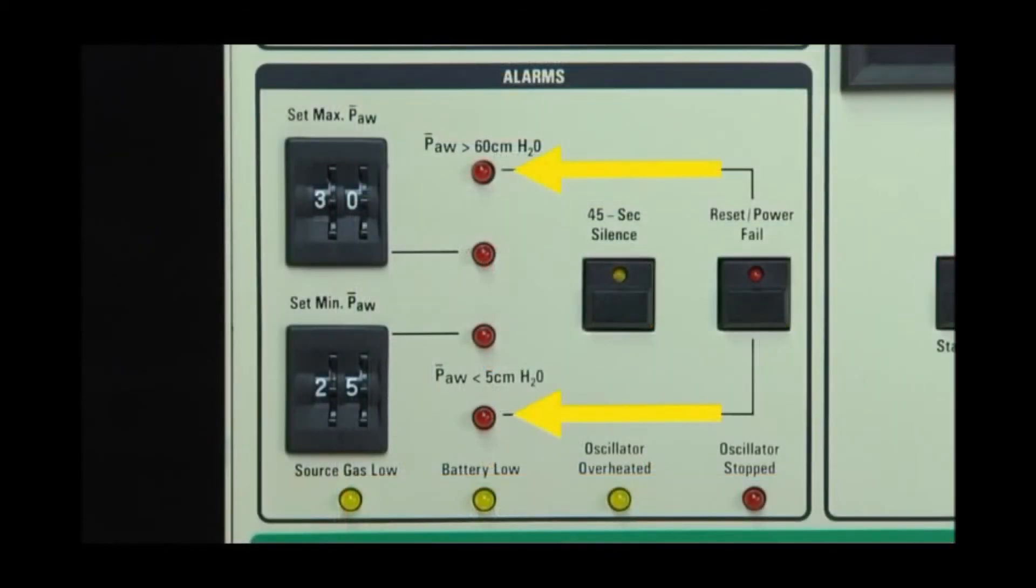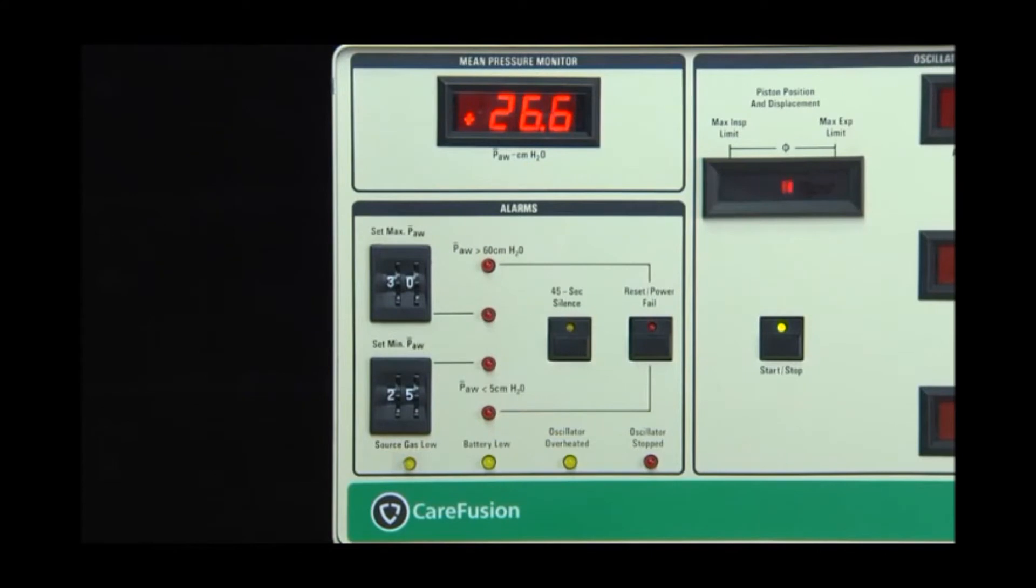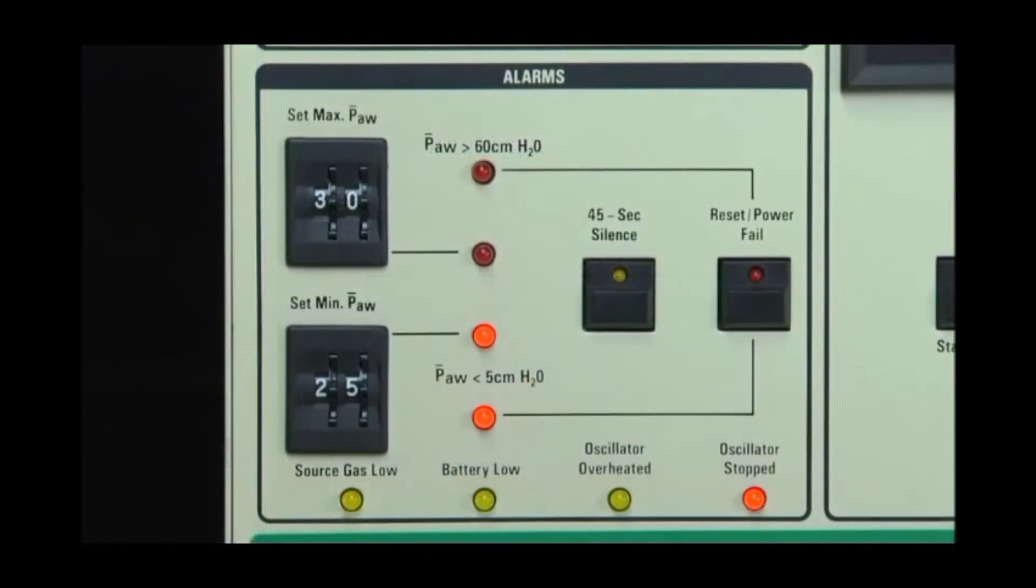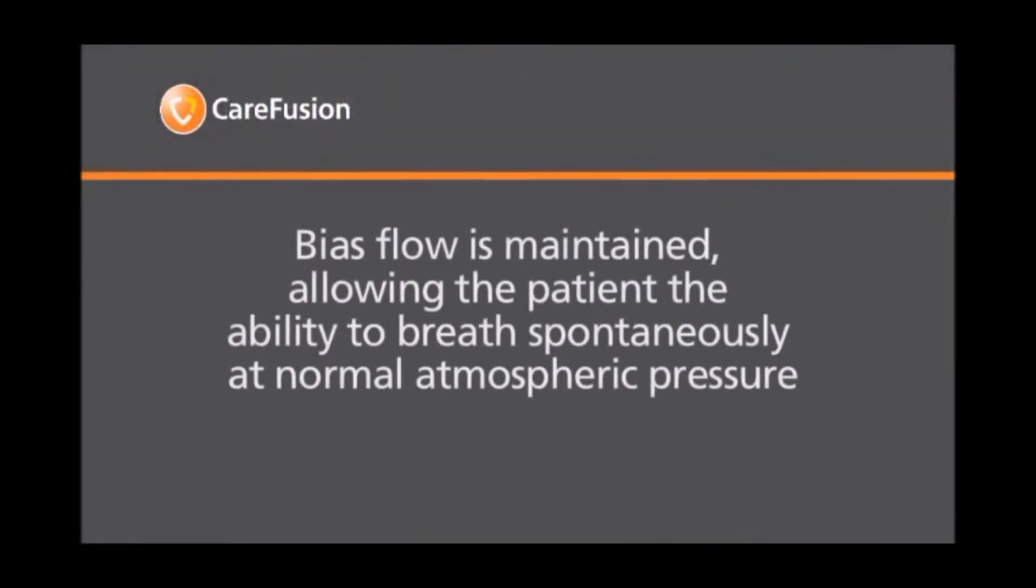Activation of the backup mean airway pressure alarms will also trigger audible and visual alarms. These backup alarms are factory preset for greater than 60 centimeters of water pressure for the high alarm and less than 5 centimeters of water pressure for the low alarm. When these alarms are triggered, the oscillator will stop and the circuit pressures will be vented to ambient pressure. Bias flow will continue. Bias flow is maintained allowing the patient the ability to breathe spontaneously at normal atmospheric pressure.